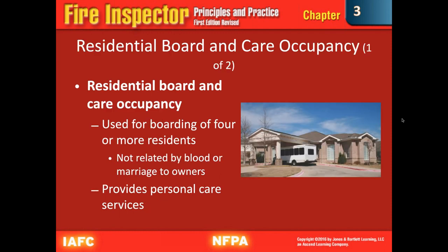Inspections for these focus on the exterior of the building, the occupant load, dwelling units, means of egress, interior finishes, protection of openings, waste chutes, which they may or may not have, hazardous areas, fire and life safety equipment, which would be like your fire alarm and detection systems, portable fire extinguishers, sprinkler and/or standpipe systems, and lighting.